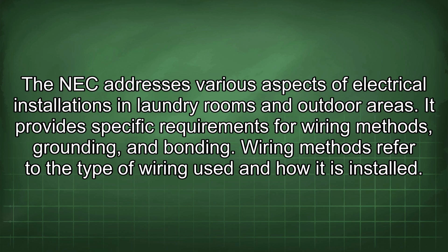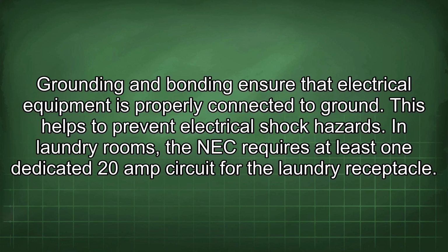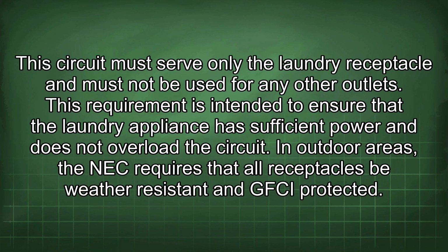Wiring methods refer to the type of wiring used and how it is installed. Grounding and bonding ensure that electrical equipment is properly connected to ground. This helps to prevent electrical shock hazards. In laundry rooms, the NEC requires at least one dedicated 20-amp circuit for the laundry receptacle. This circuit must serve only the laundry receptacle and must not be used for any other outlets. This requirement is intended to ensure that the laundry appliance has sufficient power and does not overload the circuit.